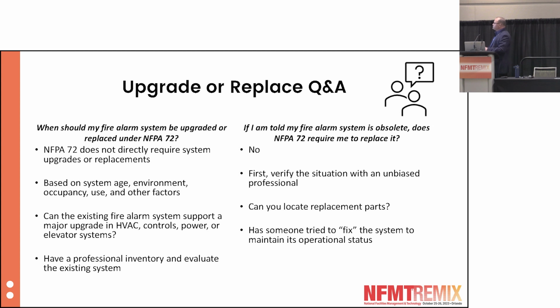The first question is, when should my fire alarm system be upgraded or replaced under NFPA 72? Well, it would be really nice if we could go to Chapter 14 and it would say every system needs to be replaced every 25 years, like I suggested. However, NFPA 72 doesn't address upgrading or replacing your system whatsoever, other than what you have to do when you do it. It's not mandating it. All of those are from the environmental and use factors we just talked about.